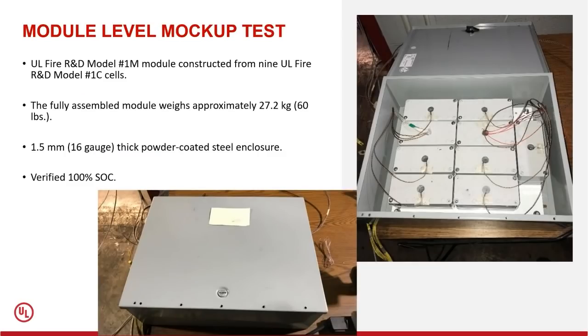This is the UL module level test utilizing the UL developed cells. You have 9 cells to the module, and again we are going to heat up one cell to drive it to runaway using an external heating coil.